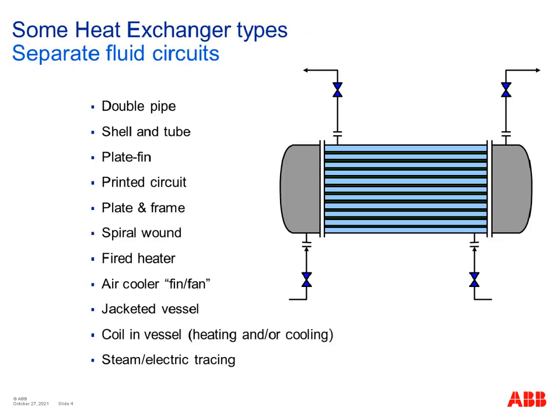So what other types of heat exchangers are there? Well, there's the double pipe, there's the shell and tube, as talked about before, plate fin exchangers, printed circuit heat exchangers, plate and frame, spiral wound. Fired heaters are a type of heat exchanger when you use a more broad definition. You've got air coolers, sometimes called fin fan units. A jacketed vessel, again, is a type of heat exchanger. You may also have coils in vessels that can be used for heating or cooling. And you also have steam and electric tracing, and this is not usually used for process stream heating, but it's still a potential heat source, so it may need to be considered in terms of pressure relief when we're thinking about pressure relief for these types of units.